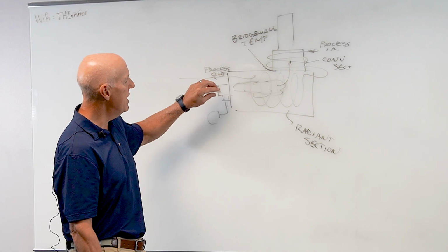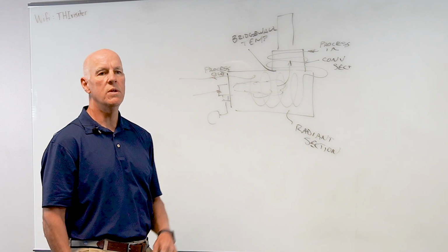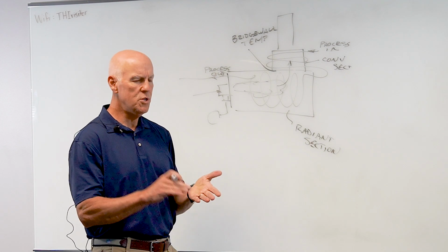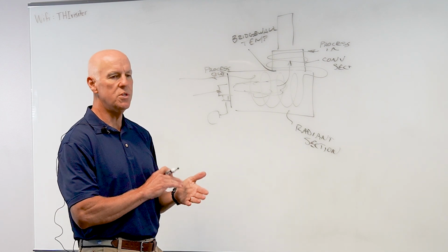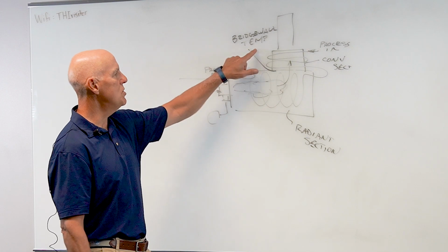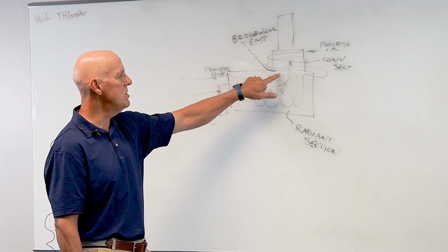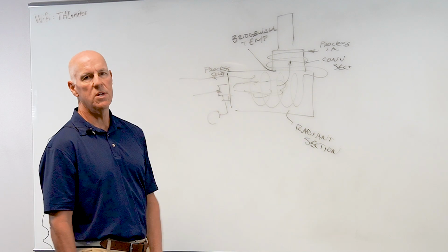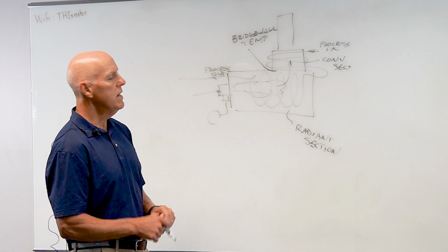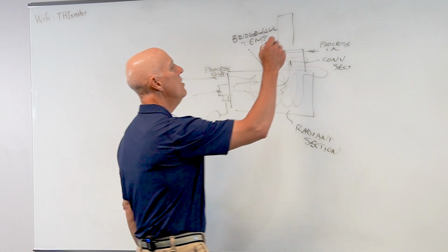And so that temperature is really most important with respect to emissions guarantees. So when we go and buy a burner from someone, we're going to say, hey, we need NOx emissions of this. And the first question they're going to want to know is, hey, what's the bridge wall temperature? Because the higher this temperature is, the higher the NOx levels.